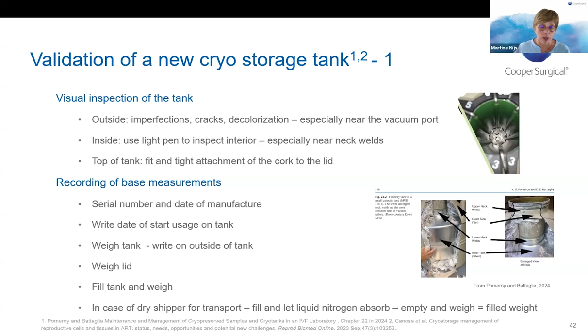And the weight is really a great tool to validate if you have leaks, if there is a stable evaporation over time. Of course, there will be evaporation. And this is also a tool, a parameter that you need to measure, the mass evaporation rate. So you will weigh, you fill up the tank, you put in the canisters, you close the tank, you weigh it, and then you will leave it for several weeks and weigh every week, for example, and see how fast the weight is changing. You can then convert that to a volume, so you will know how many liters of liquid nitrogen have evaporated.